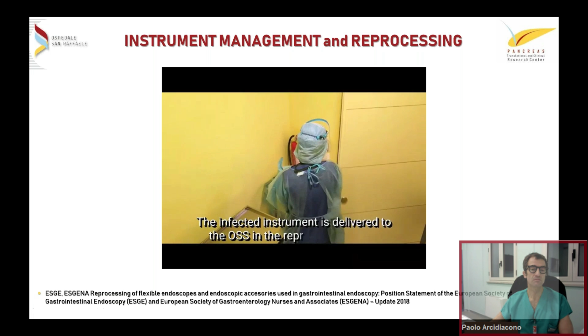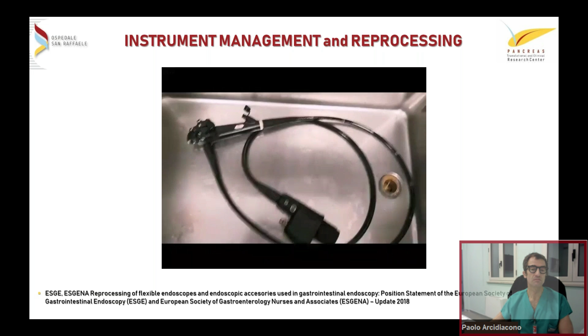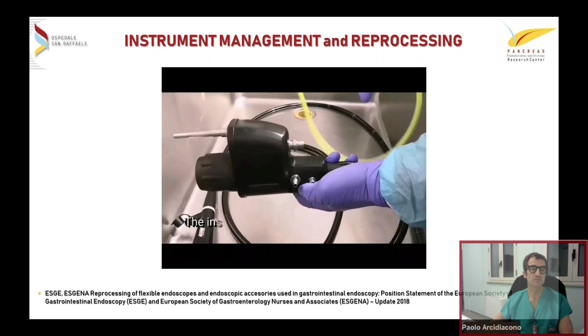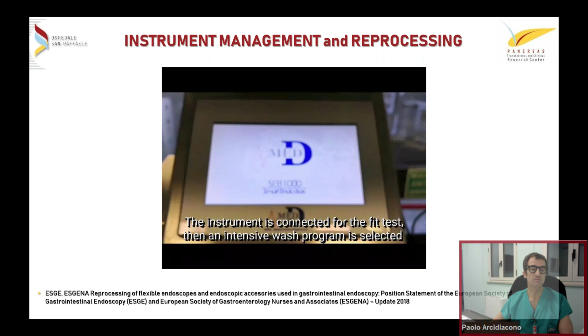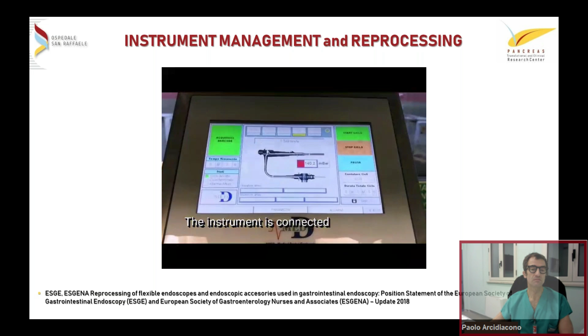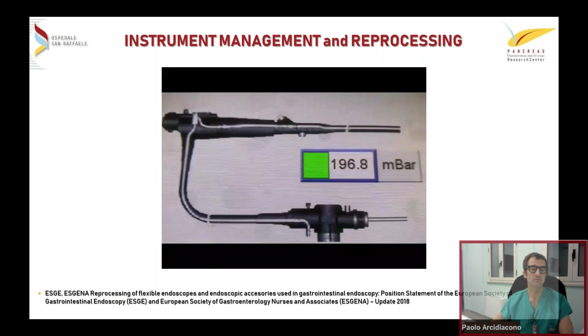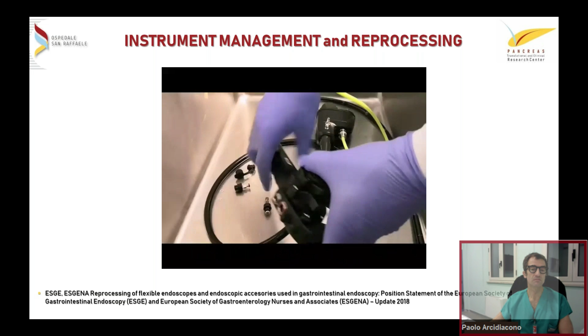This is the nurse coming from the endoscopy room into the dirty corridor that we have and entering the washing area. This is the nurse who is going to take care of the instrument. And the washing procedure is very, very important, particularly if we are dealing with an ERCP instrument, because, as you know from the literature, ERCP is the most contaminated procedure that we have to deal with in the endoscopic department. So we usually connect the instrument to this specific washing machine. This washing machine connected with the instrument can perform a perfect washing with a standard pressure of all the channels of the instrument.